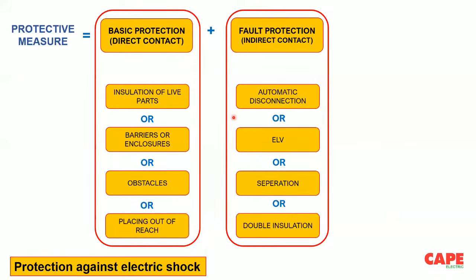So the first job of the auditor is to understand these safety measures and their application, and find out the applicable safety measure for a given location. It varies from location to location. If you have an area with computers, then sometimes you may need to go for separation. If you have a critical place with wet areas, probably you have to go for an extra low voltage situation.